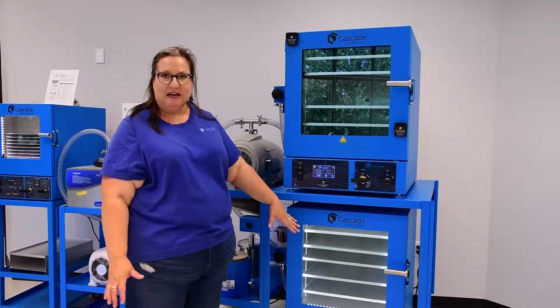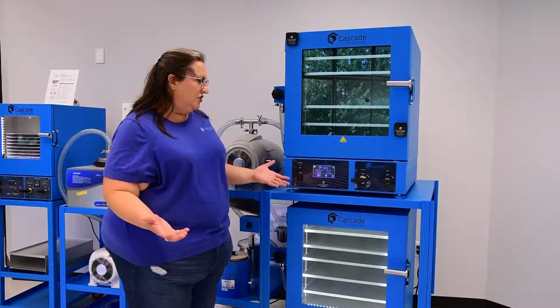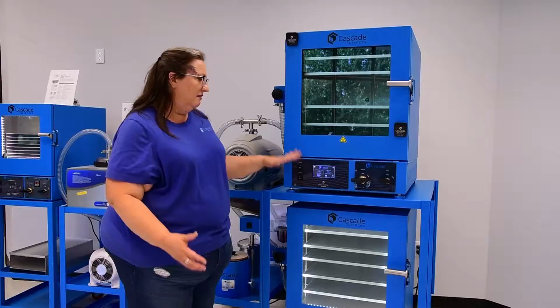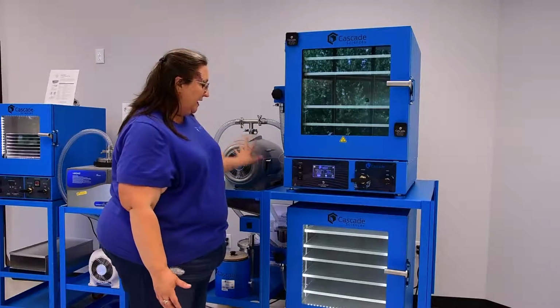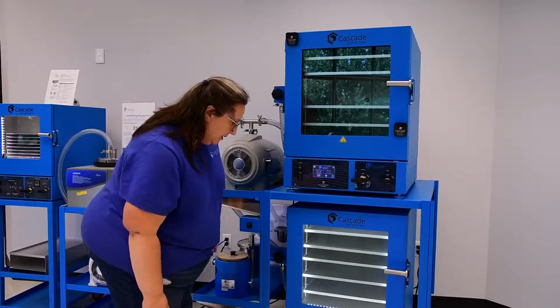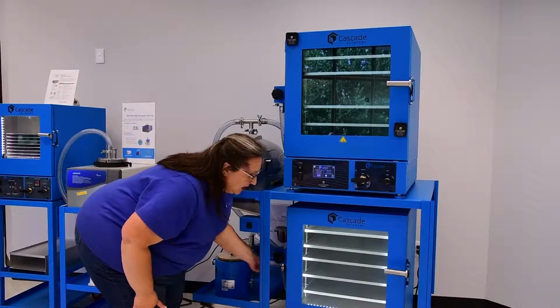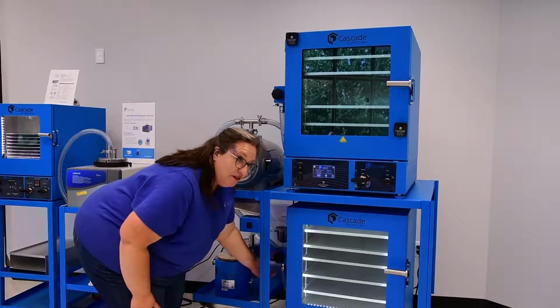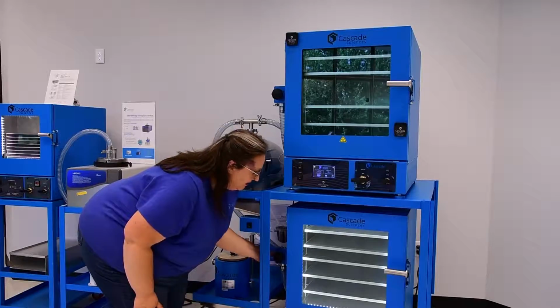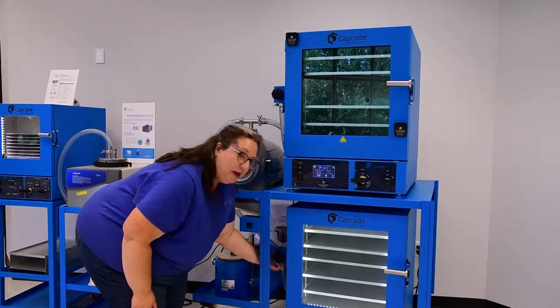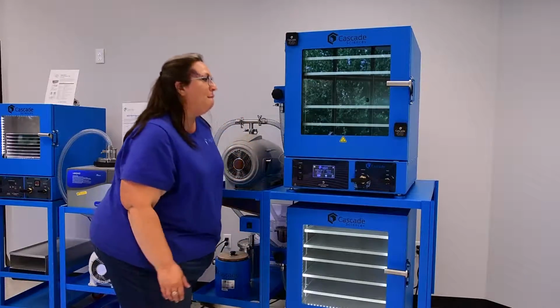We're going to go all the way down to 30 inches of mercury, 29.9, very quickly. This pump can handle both ovens with no problem at all. If I do this, you'll hear it get loud again, right? Because it's working. And the pump doesn't mind that one bit.